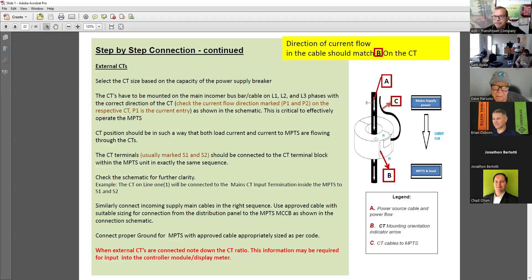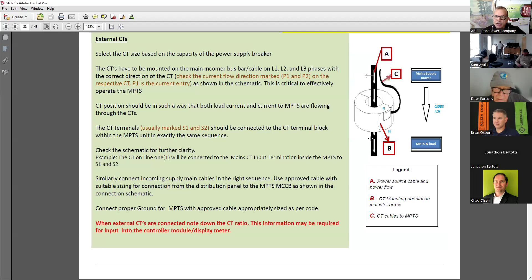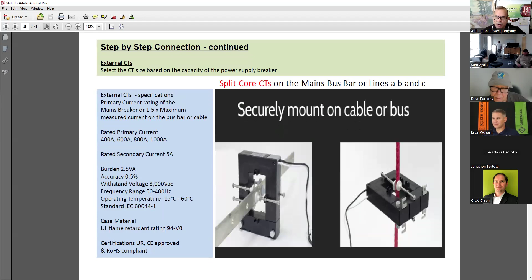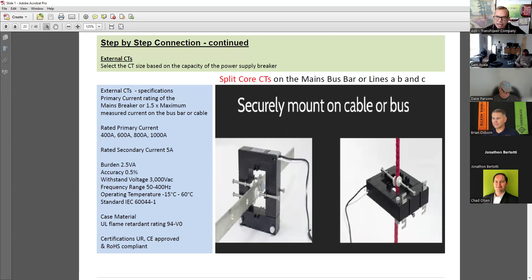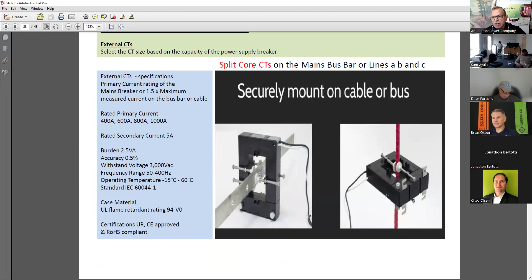So there are several types of CTs. You're saying that was a circular solid core CT. These are called split core, where you can put it around a bus bar or on a wire. We have avoided using these. They are only installed in the factory, and they used to be installed by electricians, who would have a choice to do it. But then if they did that, they had to make sure it's exactly in the center of the window in the CT. So we no longer use this, but there are several units that have these. So you need to make sure that it stays like that.